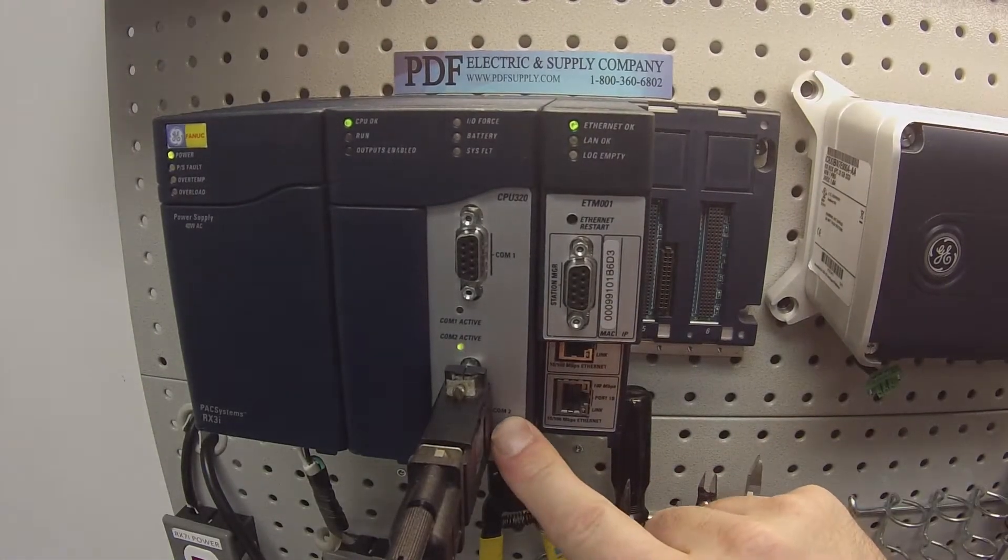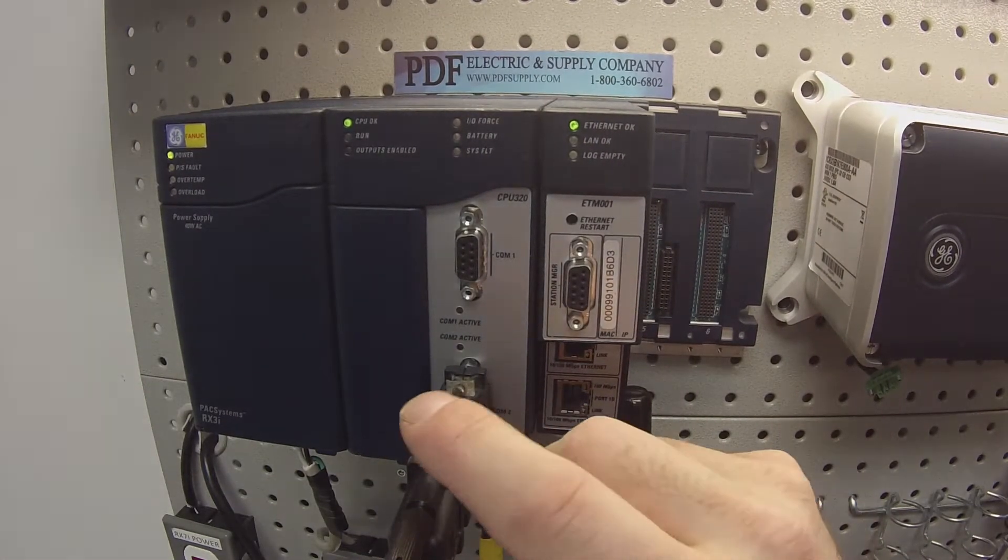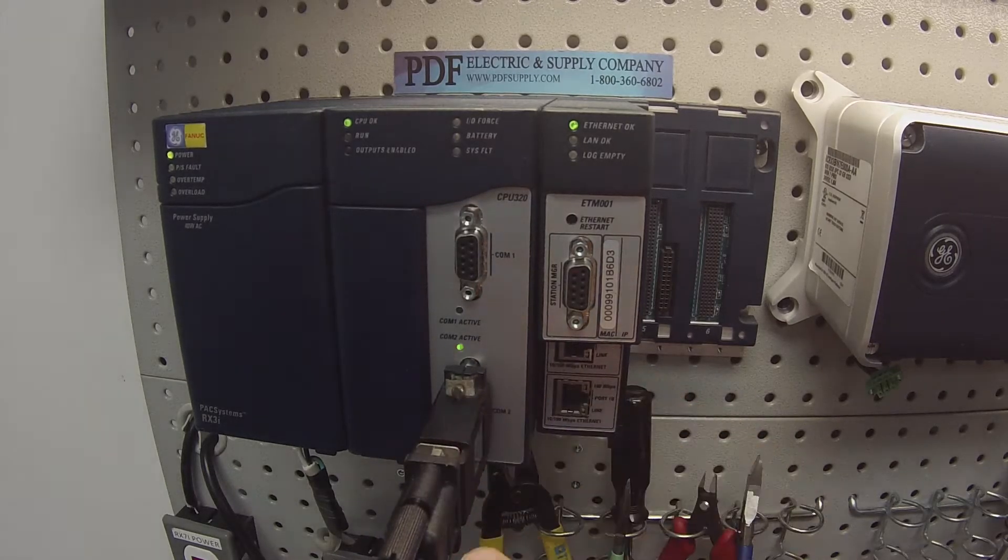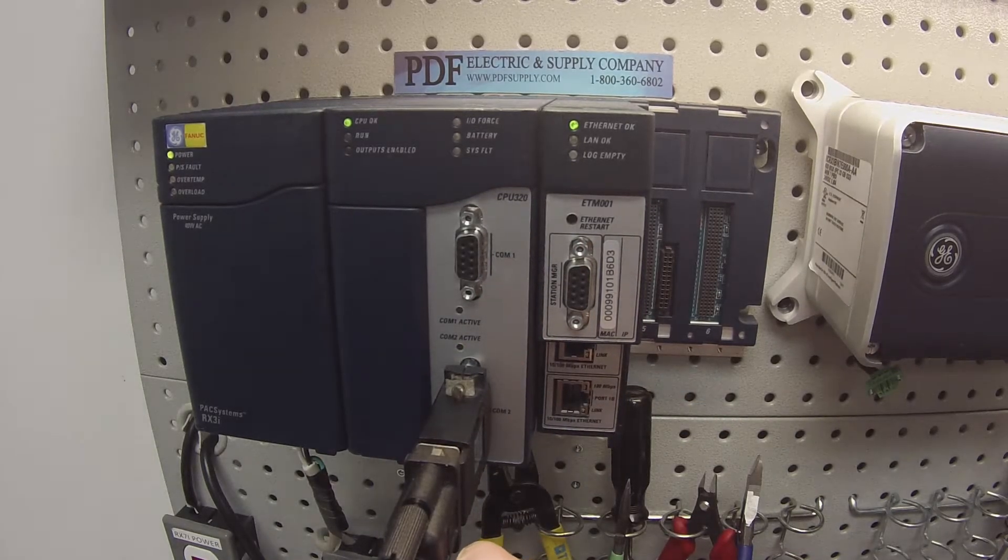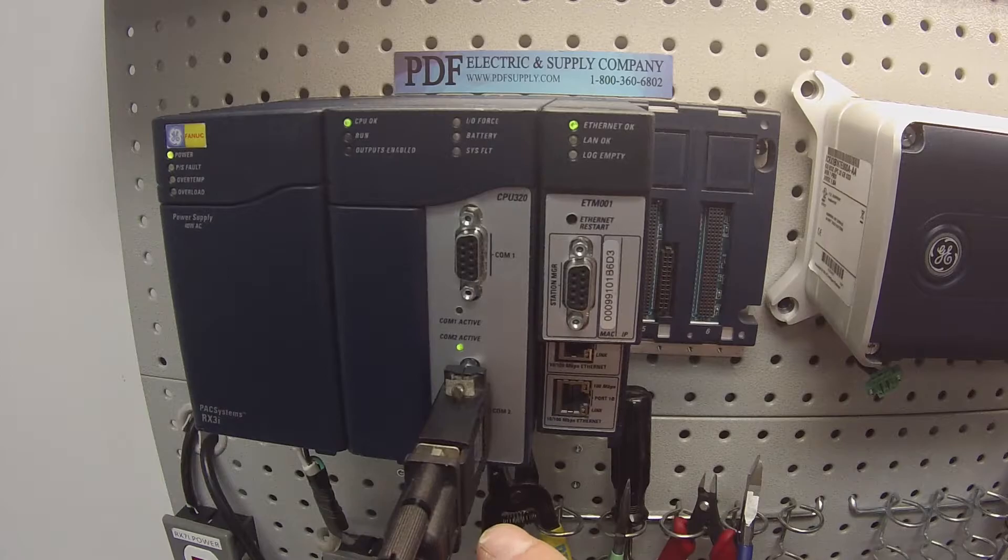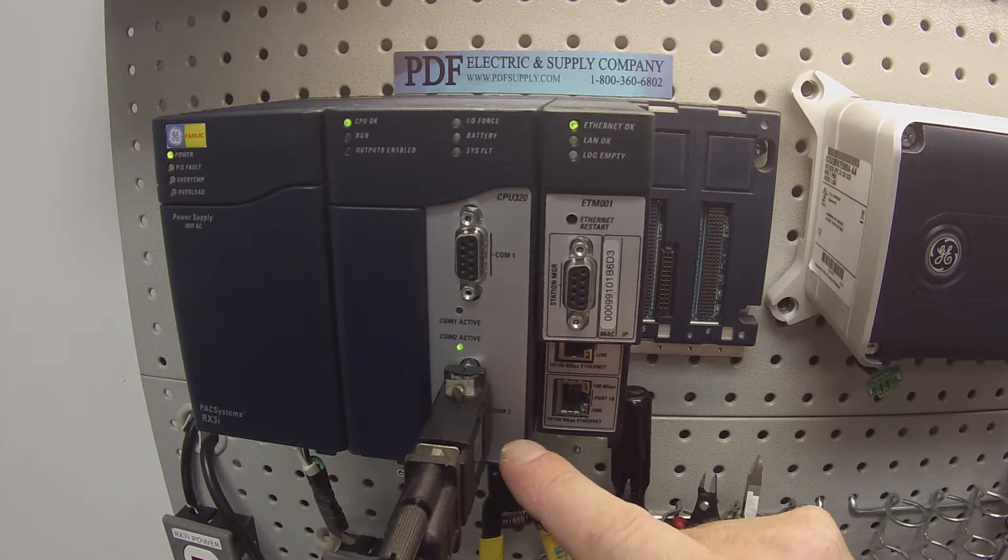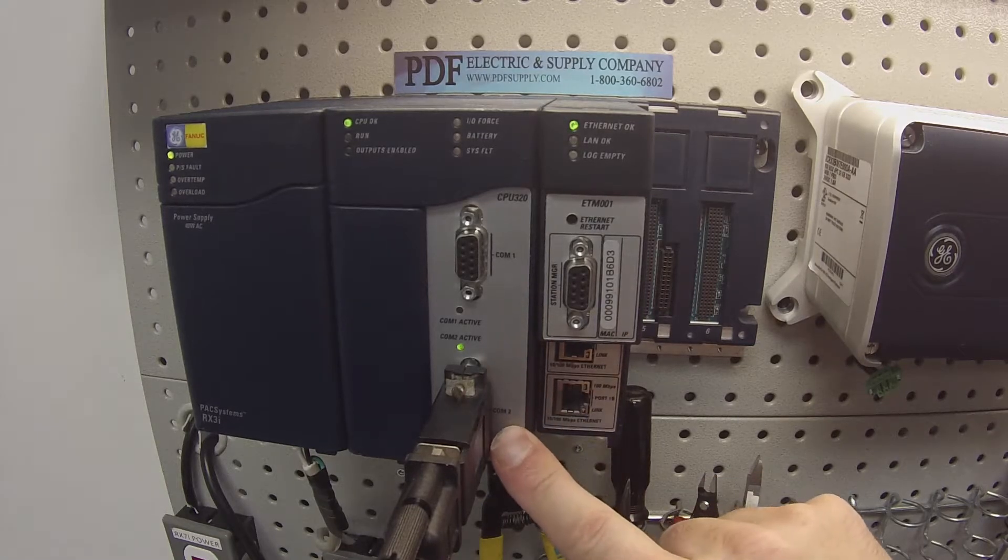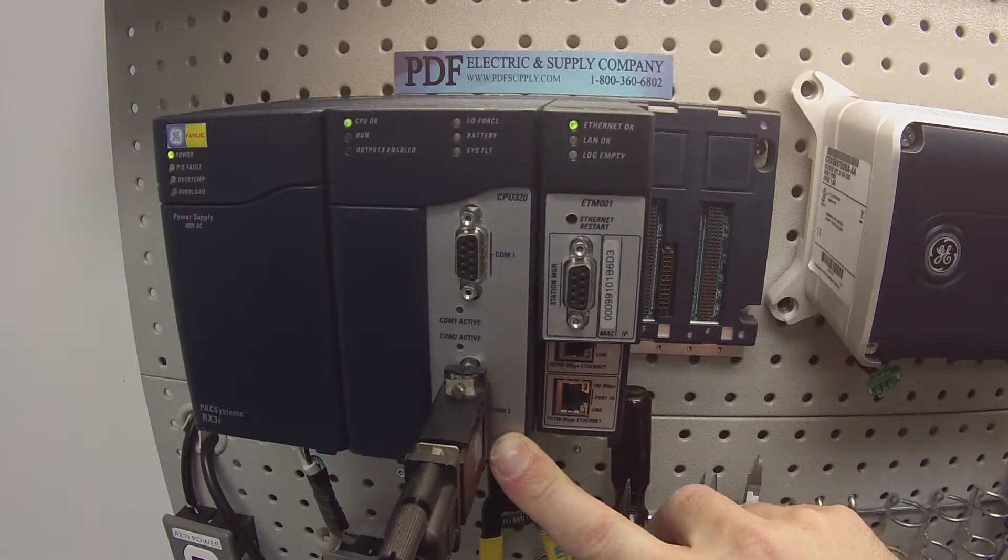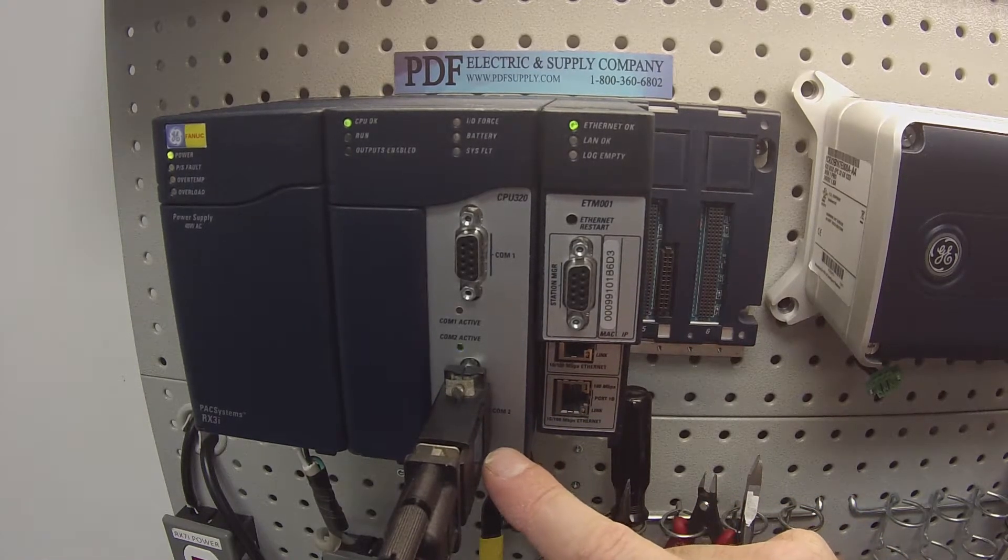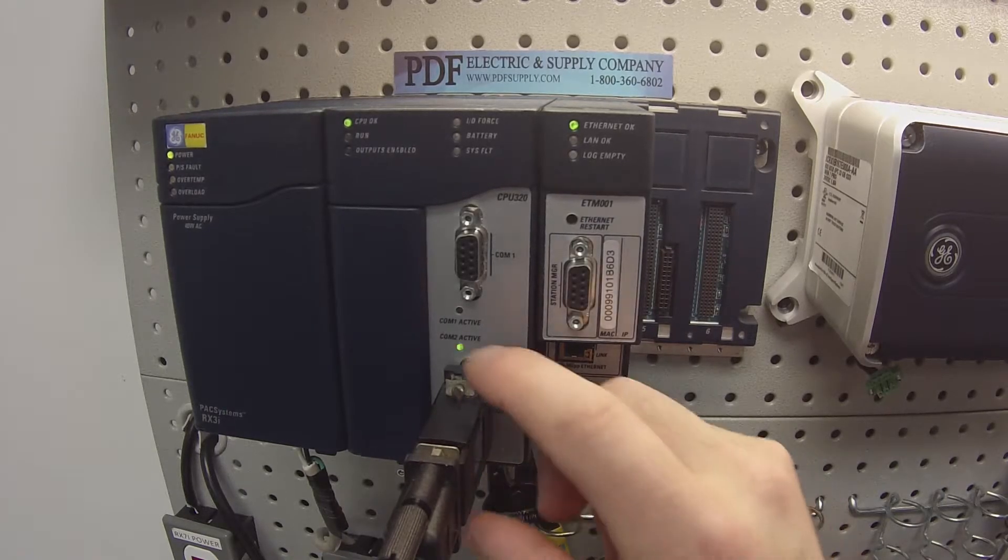As this build is in progress, I also want to explain I'm using COM port number two. I'm using an HE693CBL232 cable which is attached to the computer through the serial nine pin serial port and it's being adapted to the 15 pin port on my CPU 320 using an HE693SNP232.